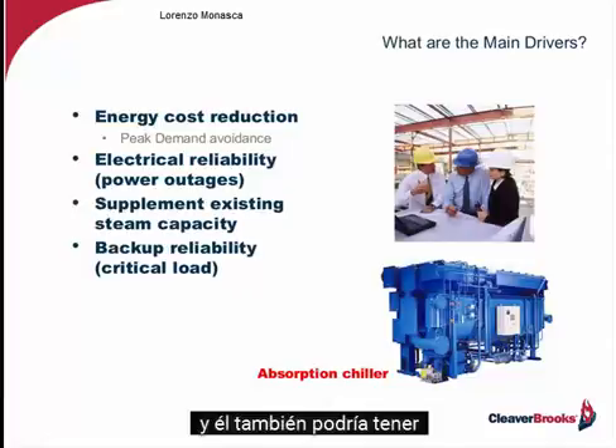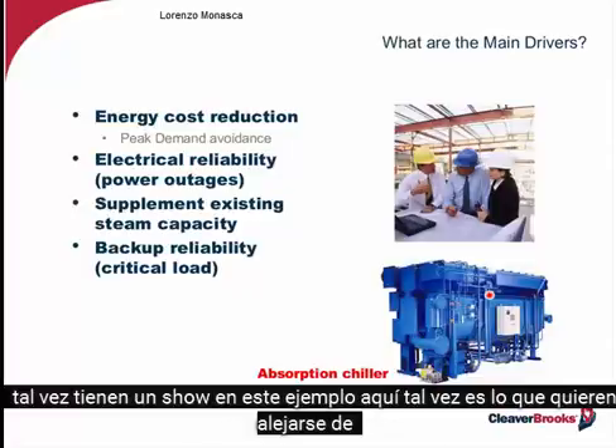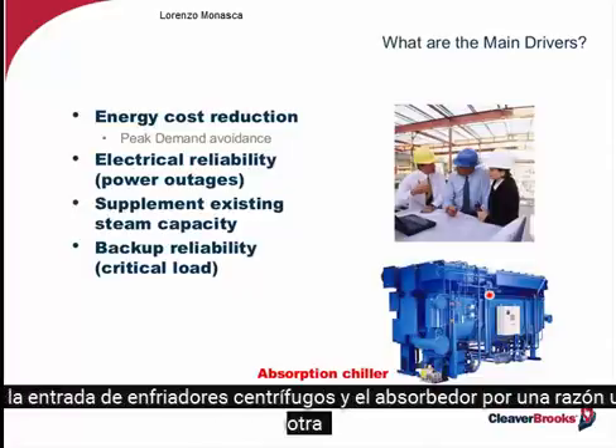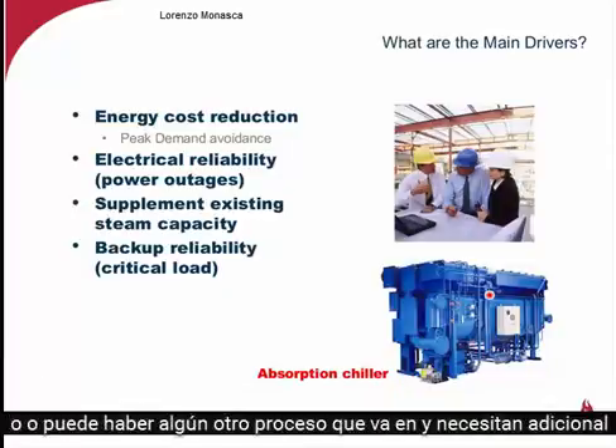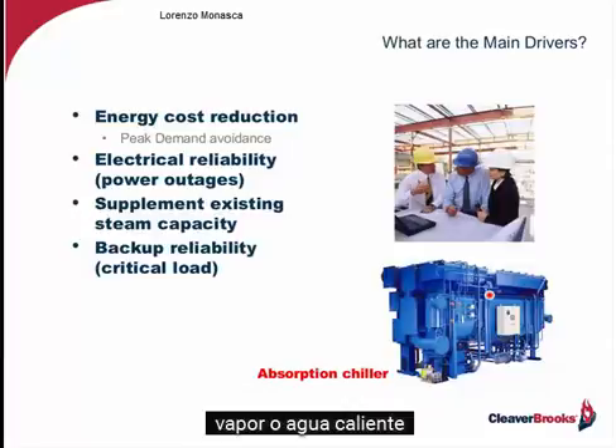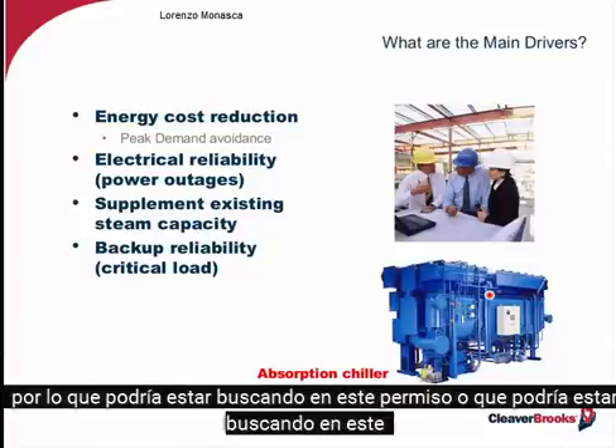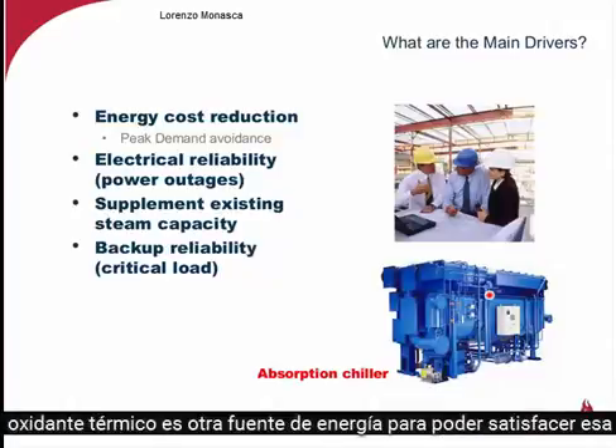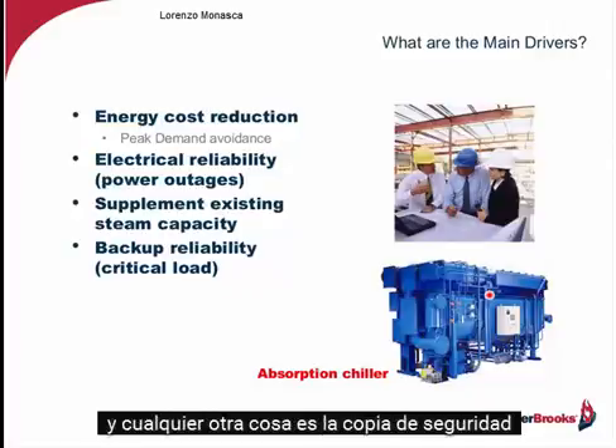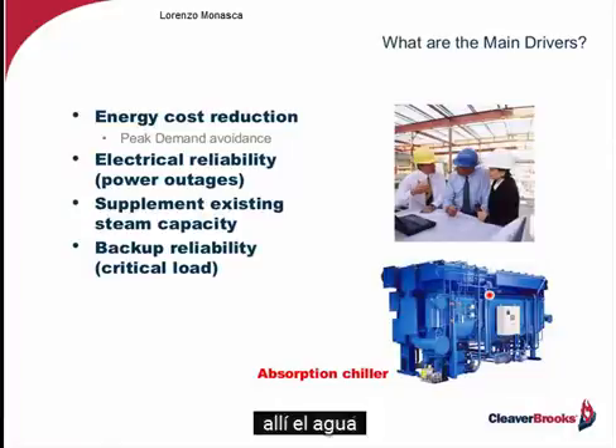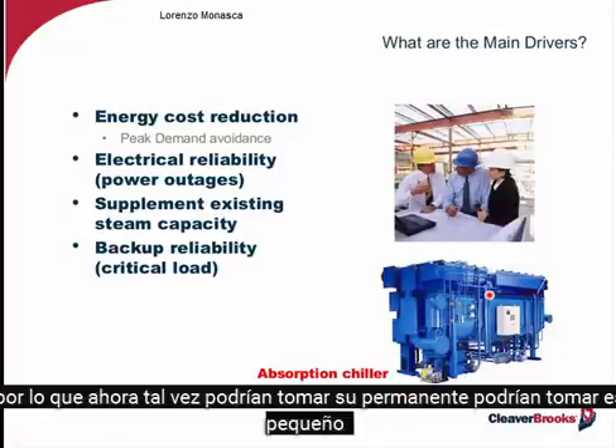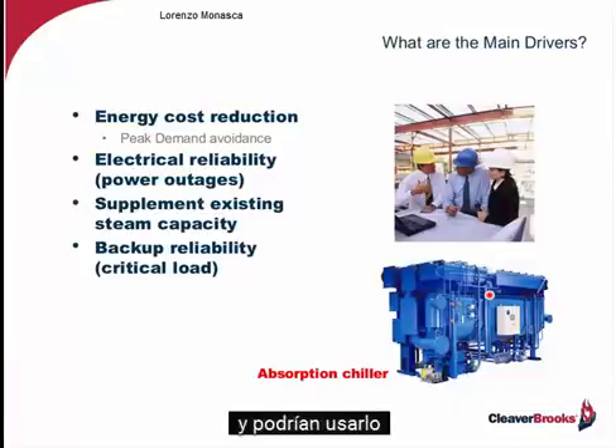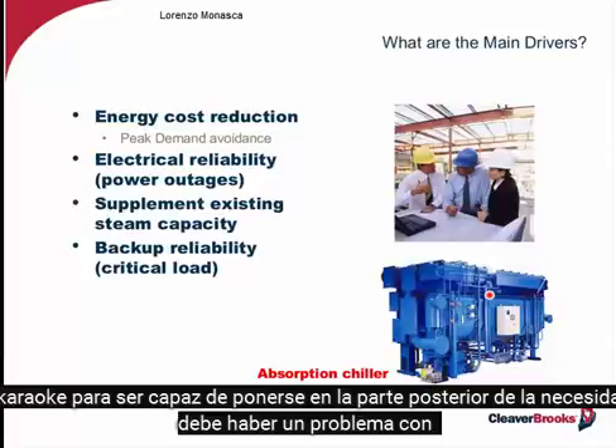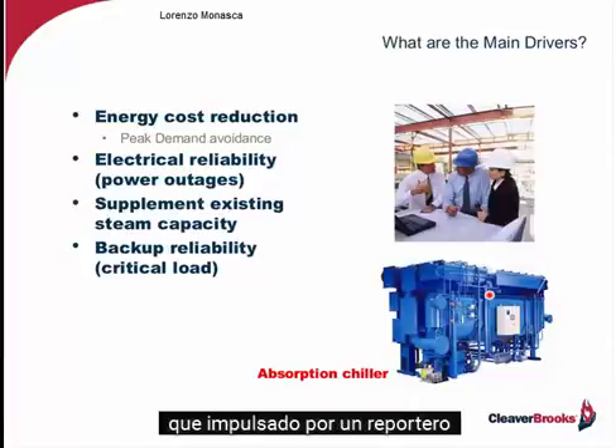And they also want to be able to supplement existing steam capacity. Maybe, as I show in this example here, they want to get away from the centrifugal chiller and put in an absorber for one reason or another. All right? Or there might be some other process that goes in and they need additional steam or hot water. So they might be looking at this turbine, or they might be looking at this thermal oxidizer as another source of energy to be able to meet that particular need. And then the other thing is the backup reliability. Their fuel-fired boiler, if that goes down, they're dead in the water. So now maybe they could take that turbine or that thermal oxidizer and use it through a HRSG to give them the backup they need should there be a problem with that fuel-fired boiler. So those are the main reasons.